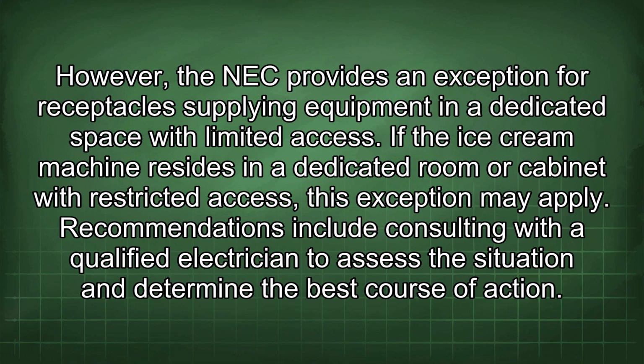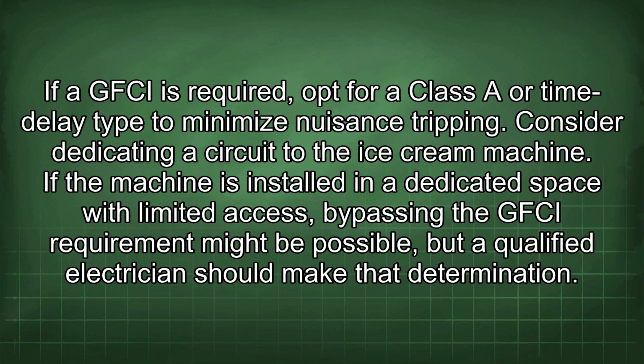Recommendations include consulting with a qualified electrician to assess the situation and determine the best course of action. If a GFCI is required, opt for a Class A or time delay type to minimize nuisance tripping. Consider dedicating a circuit to the ice cream machine. If the machine is installed in a dedicated space with limited access, bypassing the GFCI requirement might be possible, but a qualified electrician should make the determination.